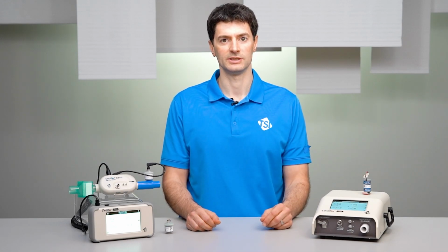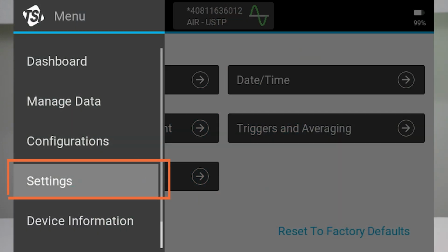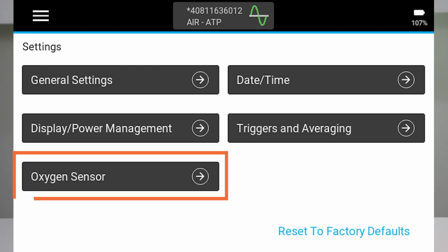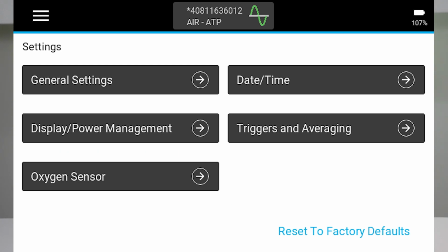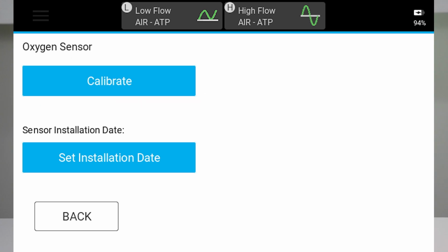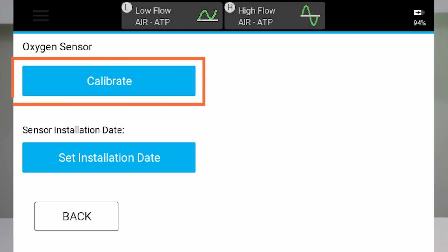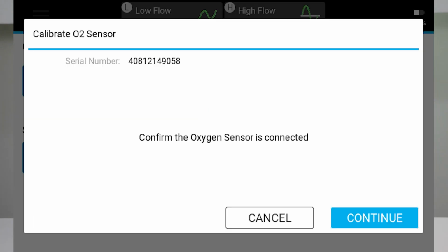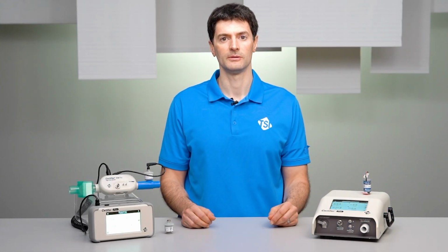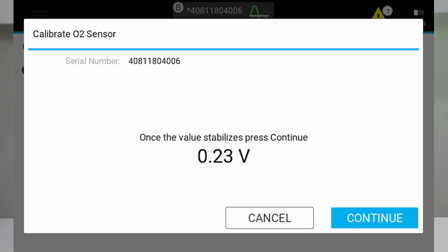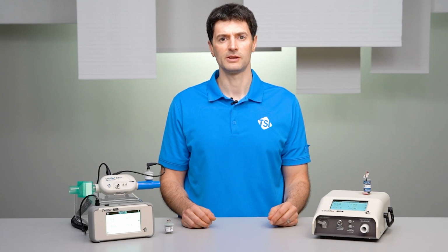To calibrate the oxygen sensor, navigate to Settings from the menu, press Oxygen Sensor, and then press the Calibrate button. Follow the on-screen prompts as the Certifier walks you through the calibration process. Confirm that the oxygen sensor is connected and expose the sensor to ambient air. Once the values displayed on the screen stabilize, press Continue. Note that this value is reading the voltage coming from the oxygen sensor and is not an oxygen concentration reading. You are just looking for the value to be stable.